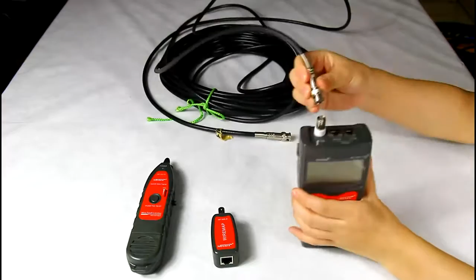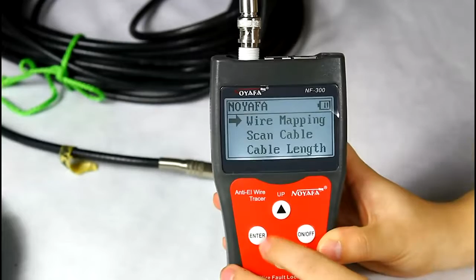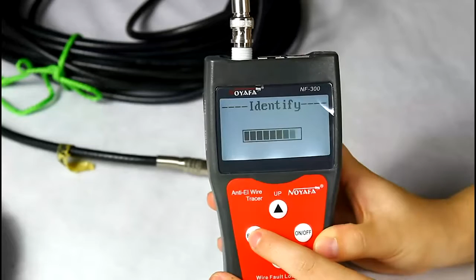Next, we are going to measure cable length for a coaxial cable, which is 20 meters. Let's connect one end to the BNC port of the emitter, and leave the other end disconnected. Turn on the tester. Here we choose BNC from the main menu and choose the cable length function. The result shows this cable is 20.3 meters.